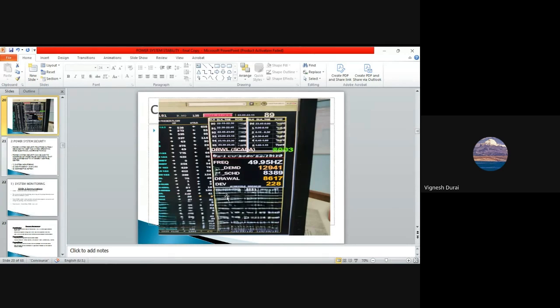This is a slide where I'm showing real time. It is not in real time; this is how we will see our monitor. See, now the frequency is 49.95. Our demand is around 12,941. This is the schedule, which will be scheduled by NLDCs. Right now they have given 8389. This schedule plus our generation should meet our demand.